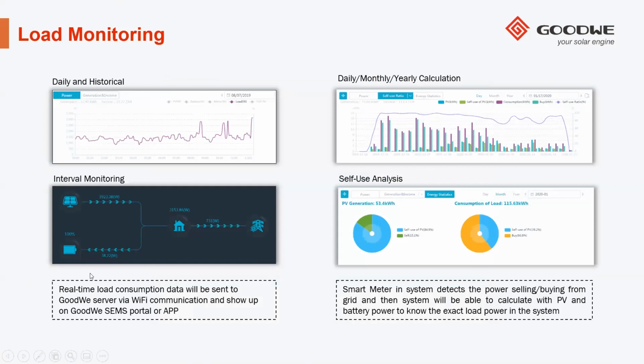On SEMS Portal, you can see a lot of your load monitoring as well as your PV production and consumption. If you select your plant as a battery storage, you'll have this interval monitoring graph that pops up at the bottom of your plant, which shows you a 5-minute snippet of what's happening on your system. You can also generate daily, monthly and yearly historical reports of your PV production. And we've also got a display of your daily, monthly, yearly calculations of your PV, your self-use, and your consumption.